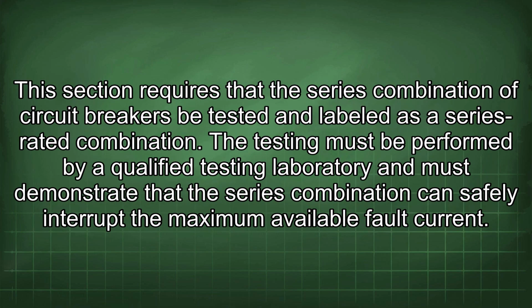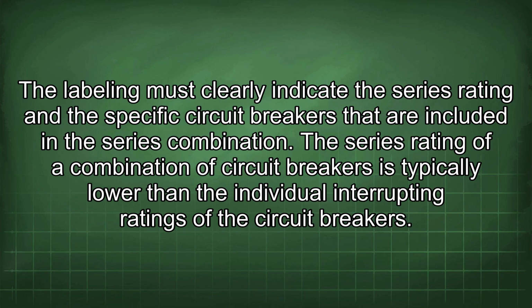This section requires that the series combination of circuit breakers be tested and labeled as a series-rated combination. The testing must be performed by a qualified testing laboratory and must demonstrate that the series combination can safely interrupt the maximum available fault current. The labeling must clearly indicate the series rating and the specific circuit breakers that are included in the series combination.